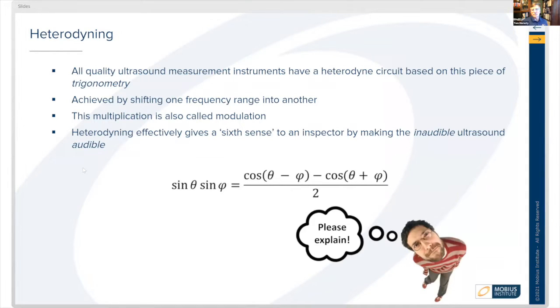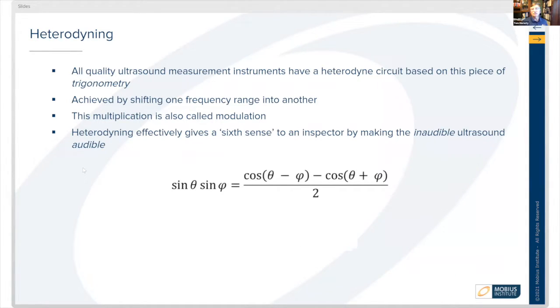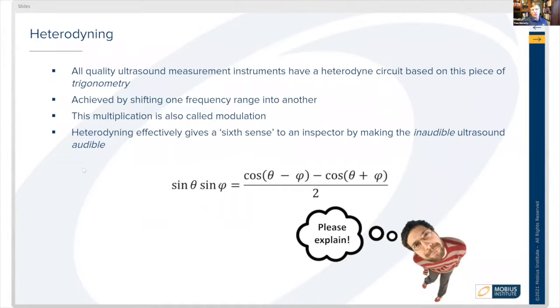So, what is heterodyning? All quality ultrasound instruments use heterodyning as a basis for how it works, and it's based on trigonometry. In this level one course, we're not going to ask you to solve equations like this, but we want to familiarize you with what it is that makes this ultrasound technology work, what's behind the box. What happens with heterodyning is we're shifting one frequency range for another. Basically, there's a multiplication that happens between two different frequencies, and you're looking at the difference and the sum of those frequencies. So, what heterodyning does is it allows us to hear the inaudible.